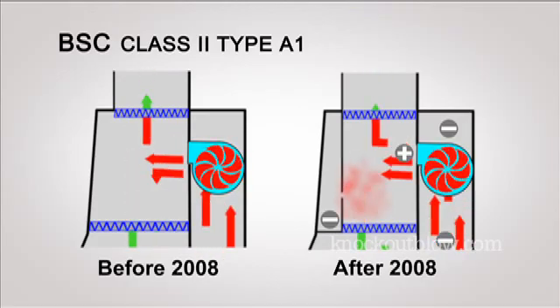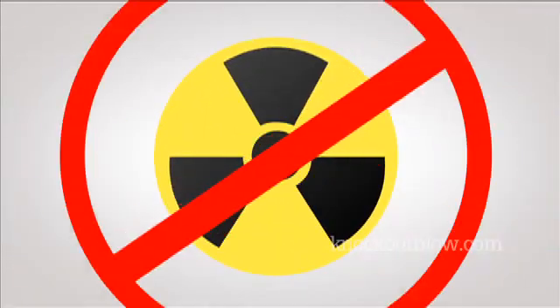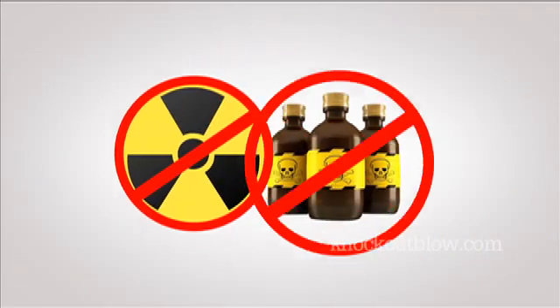Class 2 type A1 cabinets are not suitable for work with volatile toxic chemicals and radionuclides.